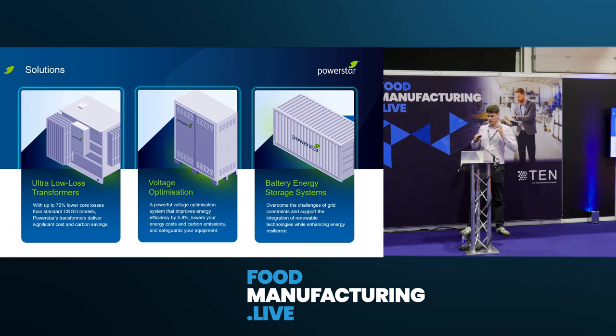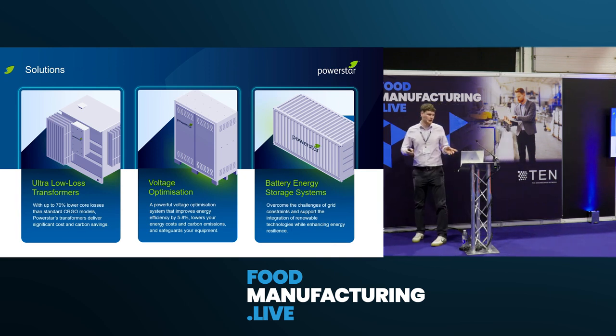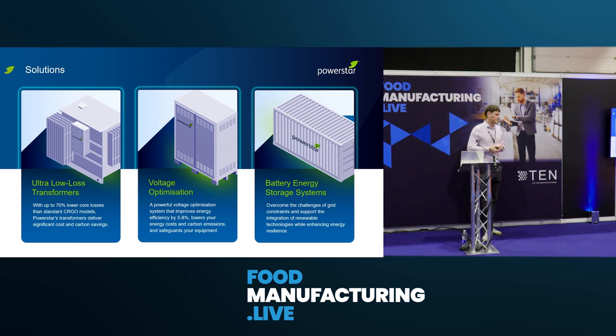So the 3 pillars - this is what I'll go on about over and over again. Ultra low loss transformers: 90% of transformers in application today are CRGO, cold rolled grain oriented transformers, where the steel or metallic laminates inside are made of this CRGO material. Eddy currents, or losses in transformers through circulating currents of the ferrous core, account for about 4% of the loss in some older transformers.